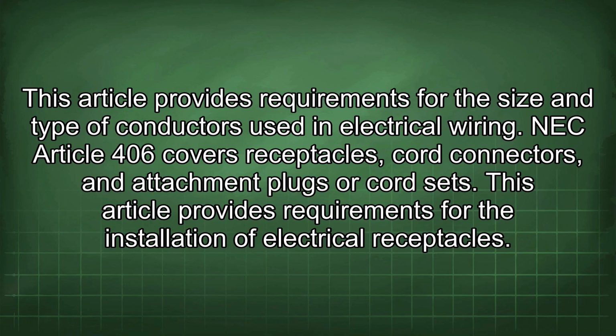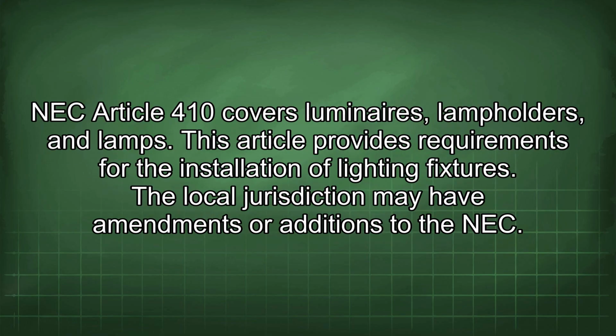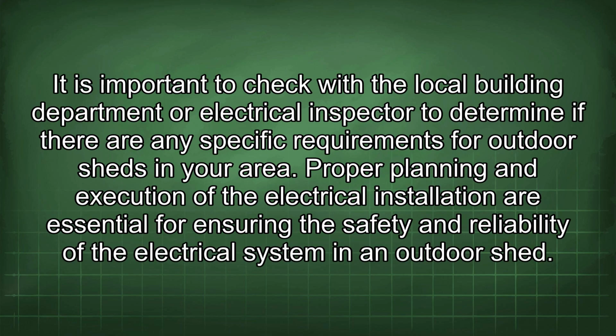NEC Article 406 covers receptacles, cord connectors, and attachment plugs or cord sets. This article provides requirements for the installation of electrical receptacles. NEC Article 410 covers luminaires, lampholders, and lamps. This article provides requirements for the installation of lighting fixtures. The local jurisdiction may have amendments or additions to the NEC. It is important to check with the local building department or electrical inspector to determine if there are any specific requirements for outdoor sheds in your area.